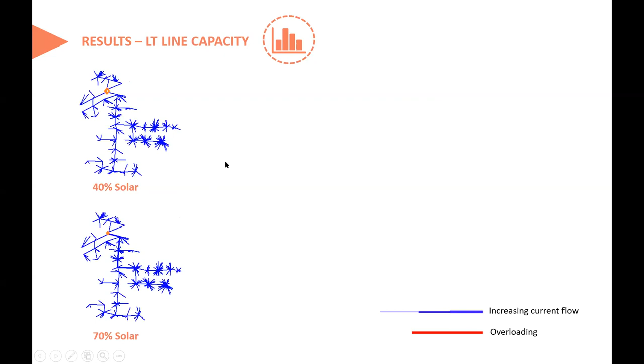With the introduction of TOD, we couldn't reduce the violation. So still there is a violation here. But with storage, you can see there is no violation. That is, the feeder can take 100% penetration without violating the feeder capacity with a properly planned storage system. On concluding the technical analysis, we can say that 100% penetration is a winning proposition with a properly planned storage system and demand side management. Also, based on the feeder's energy consumption, we can go up to 100% penetration level without violating the feeder capacity.